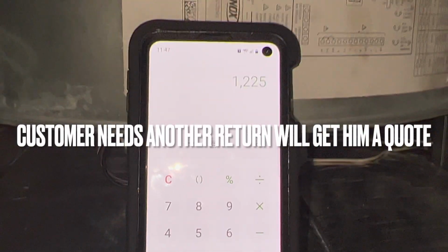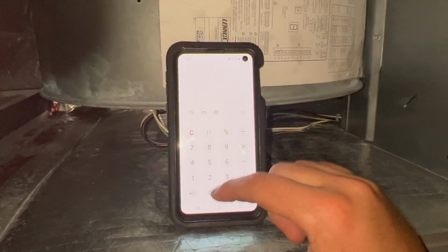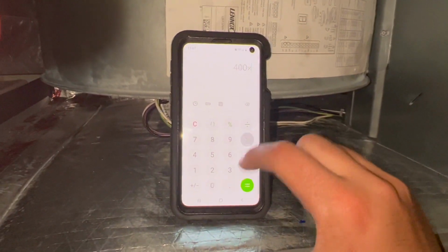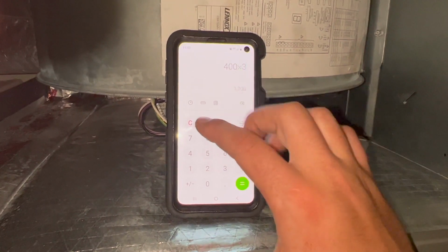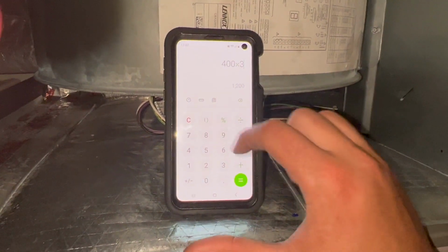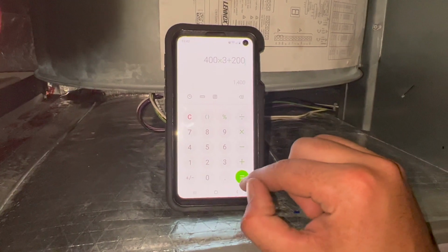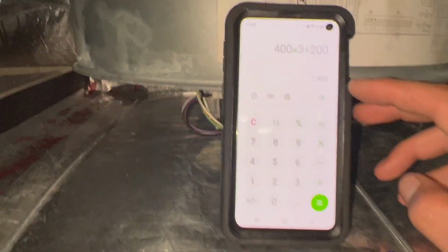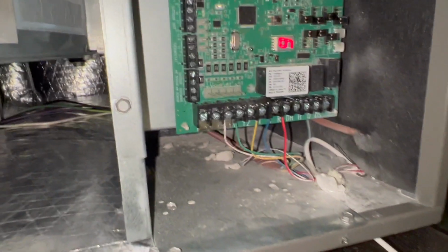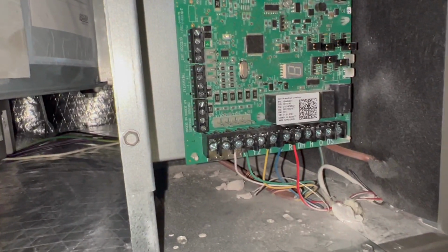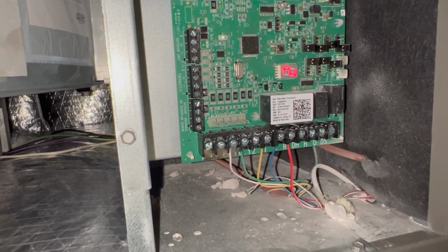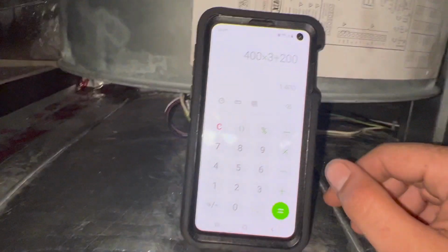but it's fine because we could have 400, which will be 400 times 3, and then plus 200, which is half of 400. So we could go up to 1,400, but I want to do 350 just to be safe. But as you guys can see, we got 1,260, which we should be good.